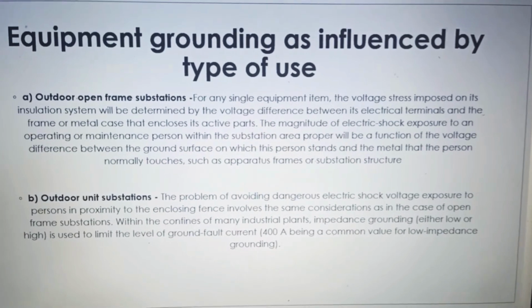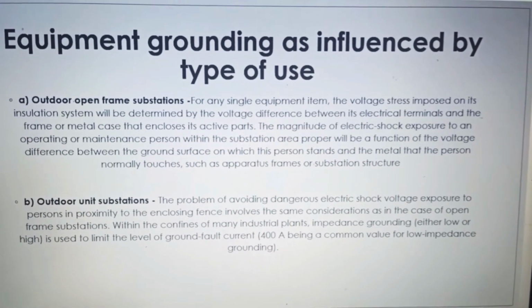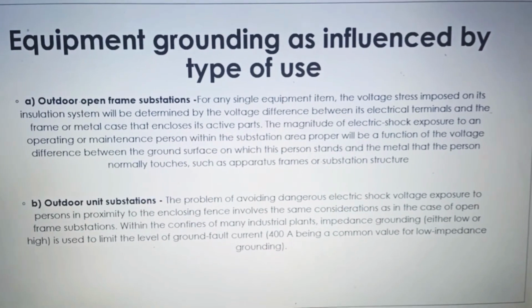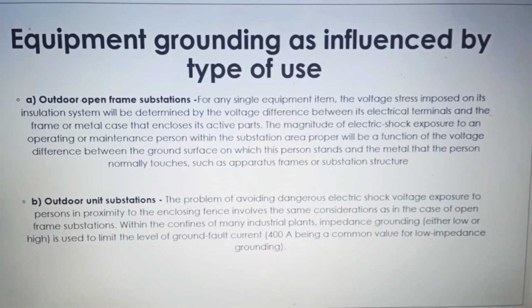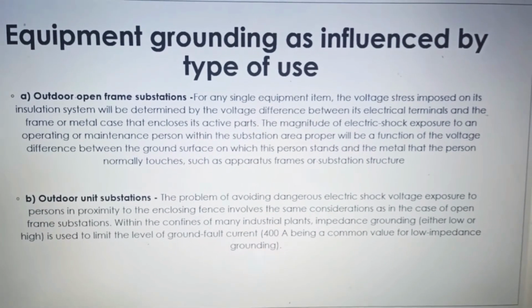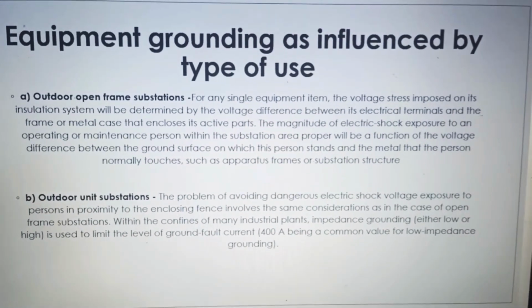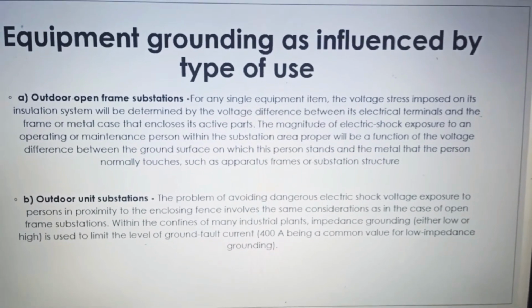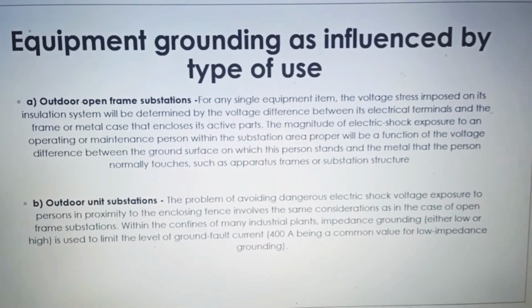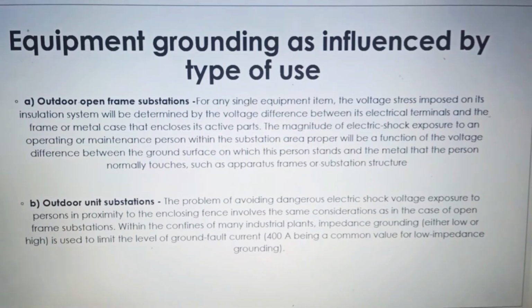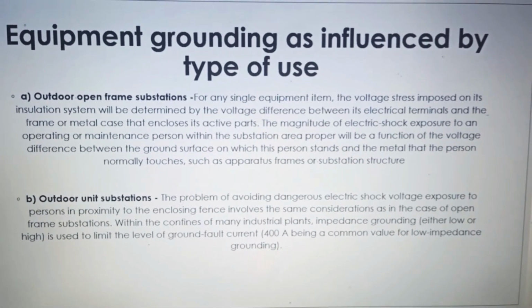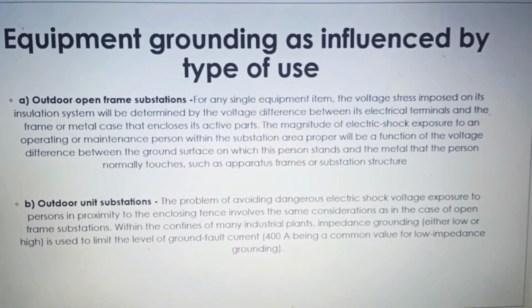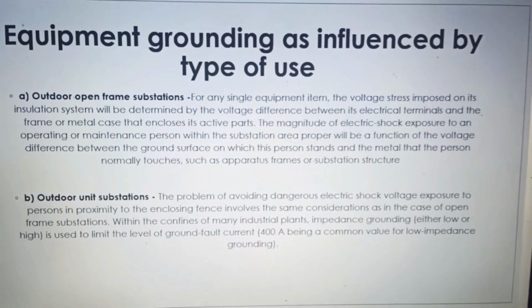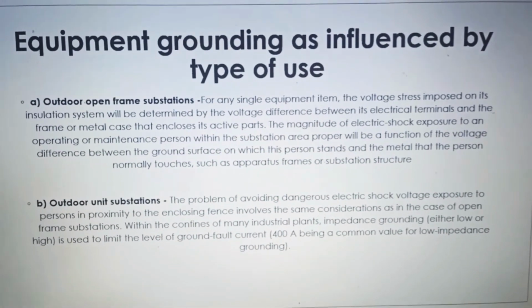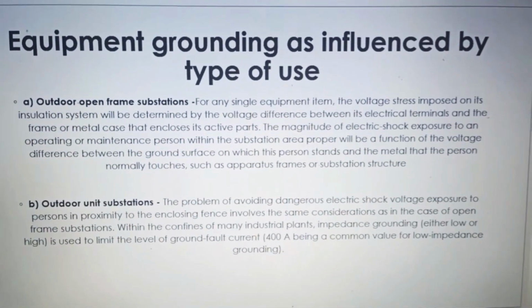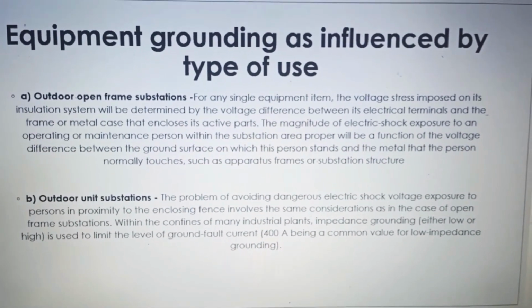It is very important to avoid a metallic extension from the station structure to some point outside of the fence area, which is exposed to contact by persons or animals. Such an extension might take the form of a water pipe, an air pipe, or a messenger cable, seemingly having no electrical function. What it does do is convey the potential of the station ground mat to the far end of the metal extension. The surface potential drops off fairly rapidly as one moves away from the boundary fence. The 50% voltage contour will be reached in a short distance away from a small station and at a longer separation distance from a larger station.